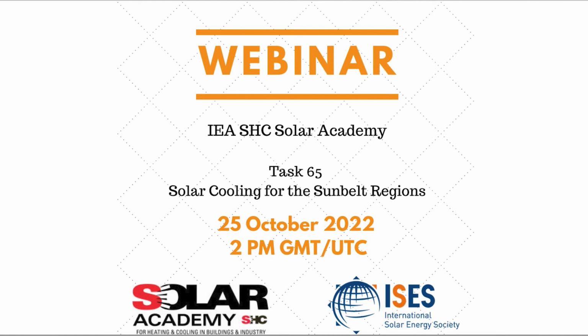Yeah, so we did a lot of studies with different experts involved in this task, and the picture today, not taking into account the different boundary conditions which have changed, including gas prices and electricity prices especially here in Europe - if you look back at the results from those different studies over the last 2 years, there's a clear trend that for small-scale systems, up to 25 kilowatt cooling capacity, PV cooling is the system which is, from an economical point of view, more or less the best, and usually cheaper than conventionally-driven vapor compressor chillers, because the prices for electricity from PV are usually less than from the grid. For larger systems, above 50 kilowatt cooling capacity, depending also on the application, solar thermal cooling systems play a bigger role, because there it's already different for the conventional vapor compressor chillers, including or combining that with PV.